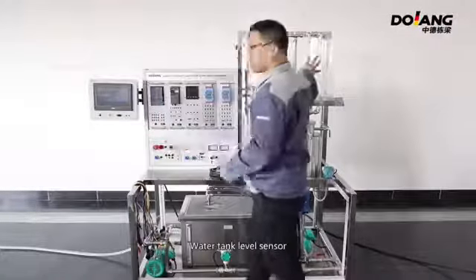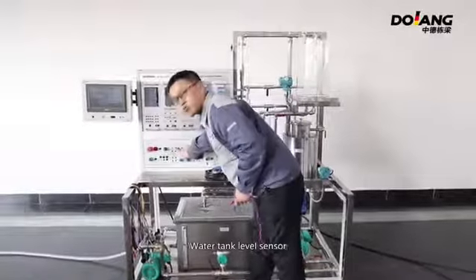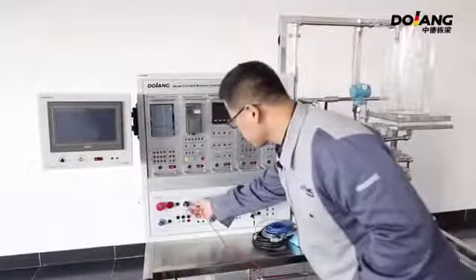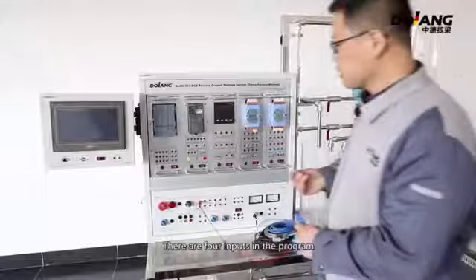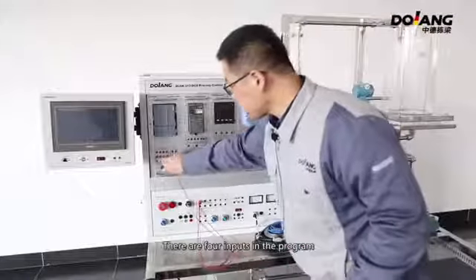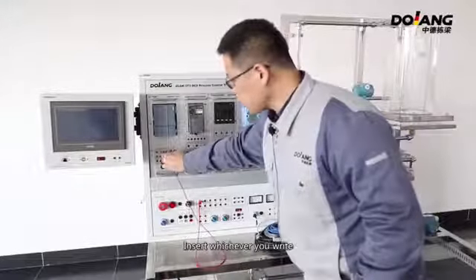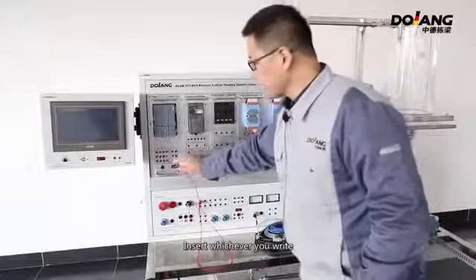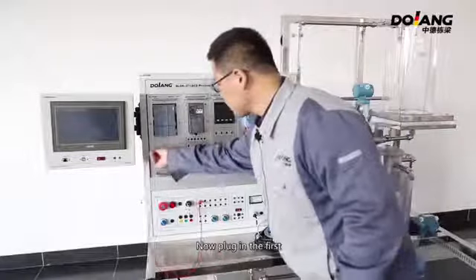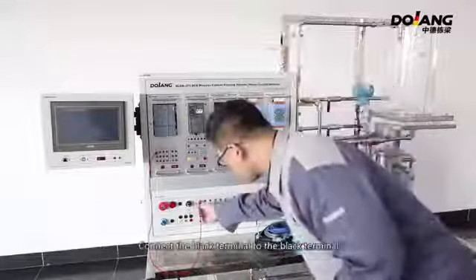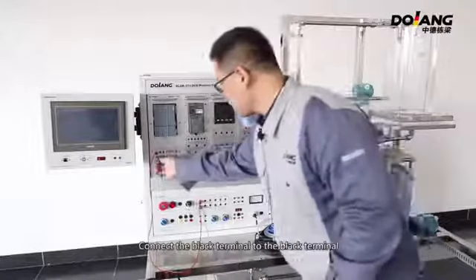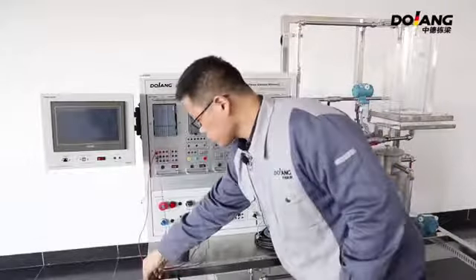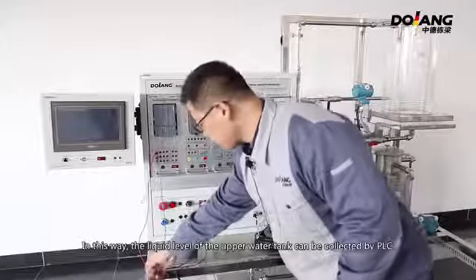Firstly, let's connect the signal wire. Water tank level sensor. There are 4 inputs into the program. Insert whichever you write. Now plug in the first. Connect the black terminal to the black terminal. In this way, the liquid level of the upper water tank can be collected by PLC.